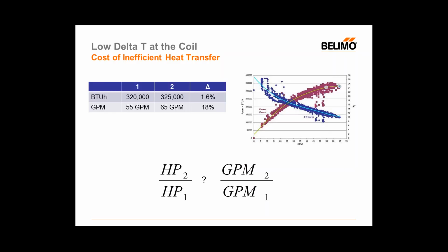And in order to understand this, we're going to take a look at what's known as the pump affinity law. The pump affinity law draws a relationship between the ratios of GPM, pump head, and pump horsepower, and scales them together. And basically, if you want to know what the increase in GPM versus the increase in pump horsepower is, you have to apply the ratio here, which includes a cube. And so 18% more water actually could wind up costing you in the neighborhood of 65% more pump horsepower or pumping dollars. And that's why we want to look at this.